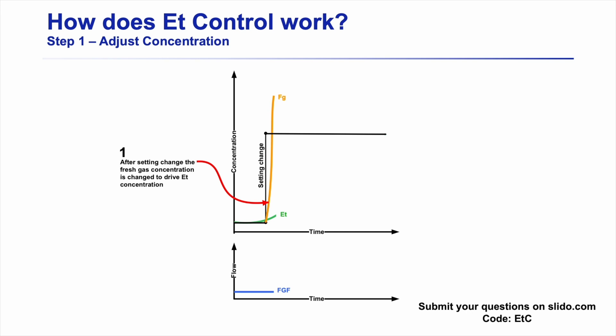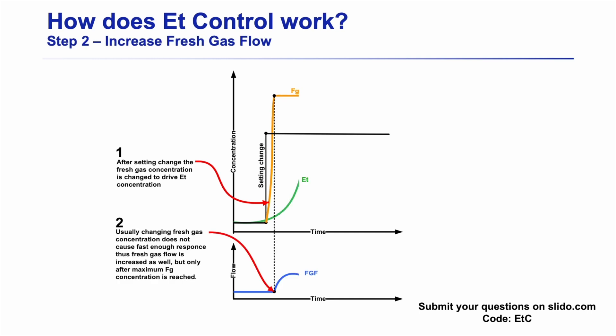What actually happens when you make a setting change? On the top we show the concentration — what the anesthetic agent vaporizer is doing — and on the bottom, the fresh gas flows. In step one, you set a new agent value and we open the vaporizer all the way. That's the same thing you would try to do if you're driving agent into the circuit — vaporizer all the way open while your fresh gas flow stays low. In step two, once the vaporizer is all the way open, we increase your fresh gas flow — two liters a minute, three liters a minute, something like that. We still put a lot of effort into keeping that fresh gas flow relatively low.